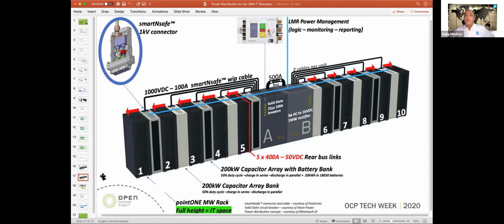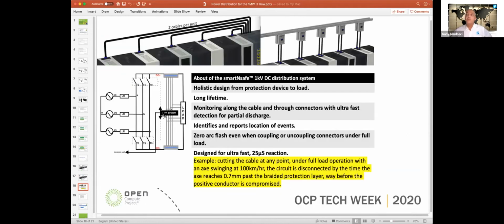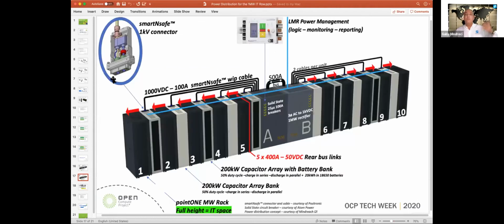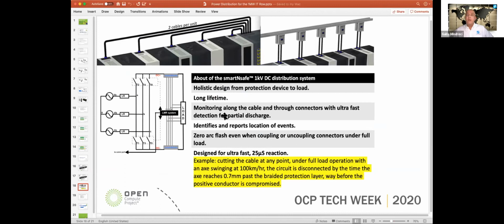But also on the backbone of this system is a monitoring system that's used for logic monitoring and reporting. This makes this whole system a holistic design from protection device all the way to the load. So you cannot just take any connector or any cable and make it work. They have to work together, and the cable is designed to work with the connector together, and so on. The logic and the monitoring and reporting system is able to detect partial discharge continuously. And as soon as partial discharge is detected, the system will know what to do, and that event would be communicated to the load and to the source simultaneously, and therefore redundancy can take place.